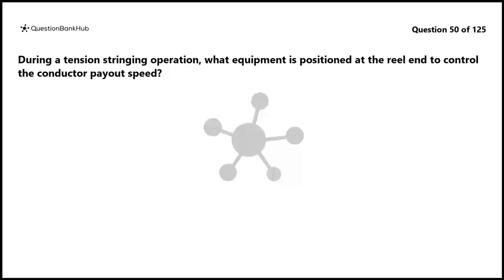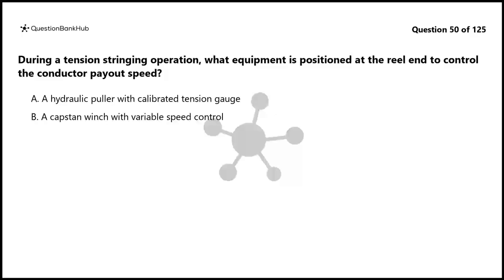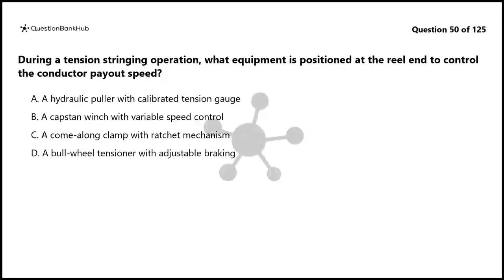Question 50. During a tension stringing operation, what equipment is positioned at the reel end to control the conductor payout speed? A. A hydraulic puller with calibrated tension gauge. B. A capstan winch with variable speed control. C. A come-along clamp with ratchet mechanism. D. A bull wheel tensioner with adjustable braking.